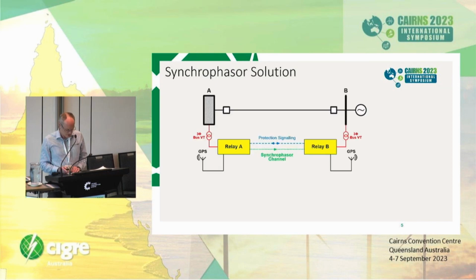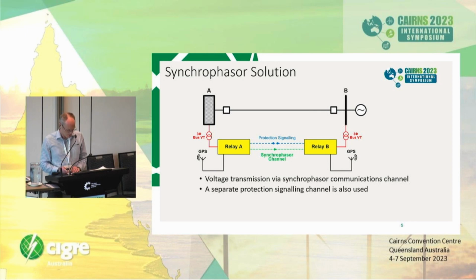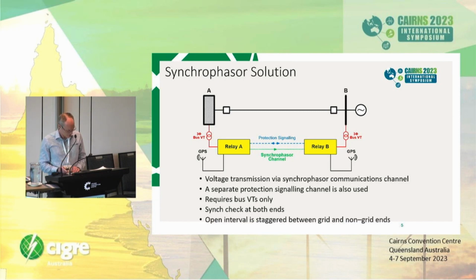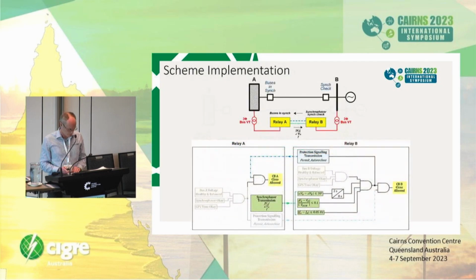An alternative solution is to use a synchrophasor synchronism check scheme. Voltage signal transmission is via a separate synchrophasor communication channel. A separate protection signaling channel is also used for permissive voltage checks due to the slow data refresh rate of the synchrophasor channel. It therefore requires only three-phase bus VTs at each end of the circuit. A synchronism check is made at both ends of the circuit, and the open interval is staggered between the grid and non-grid ends. The scheme uses synchrophasers and high-speed communication channels. I will briefly describe its implementation in Transpower's initial design.